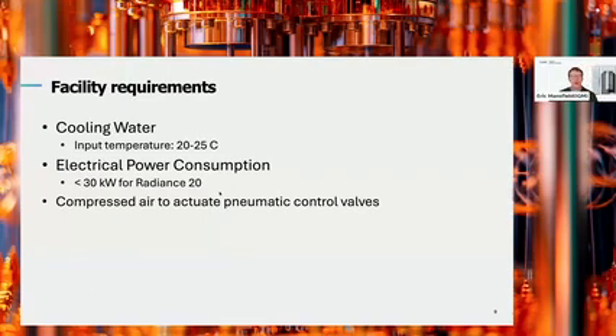Our quantum computers use input water with a temperature between 20 and 25°C. Most HPC centers we've spoken to have either 2 or 3 different water temperature loops, where this 20 to 25°C is one of the lower temperature loops, and there's usually a 30 to 45°C loop as well for less sensitive applications.